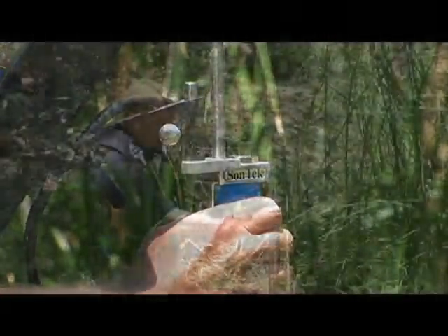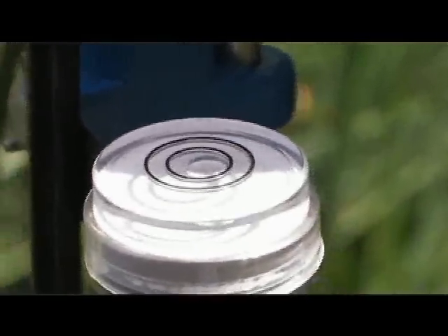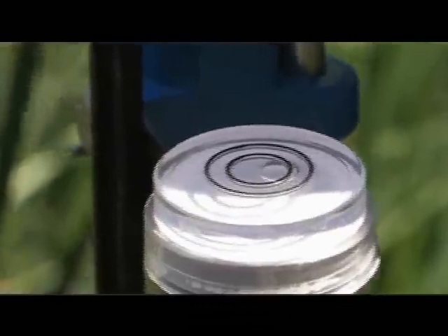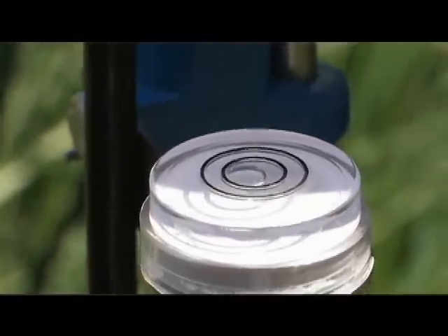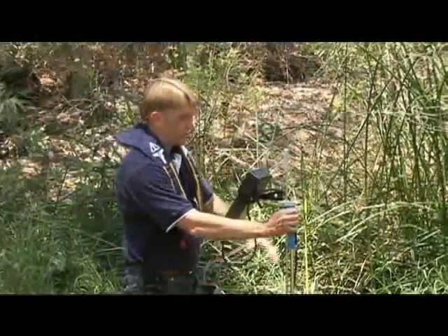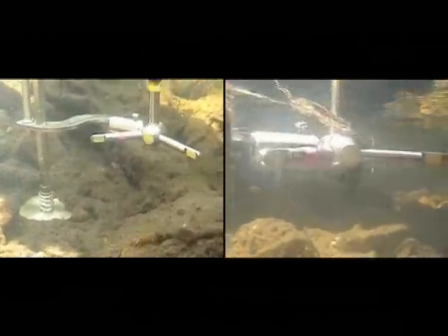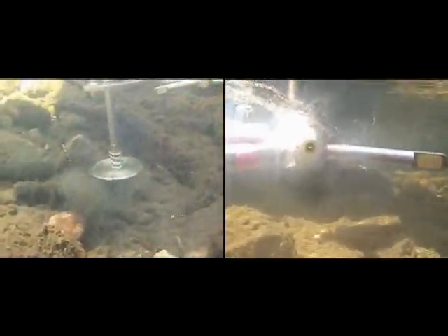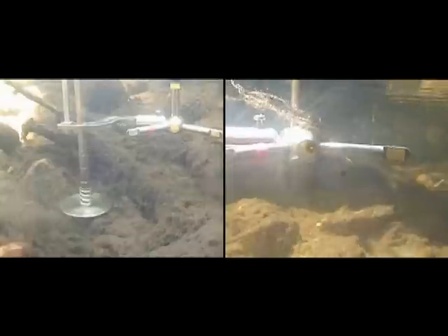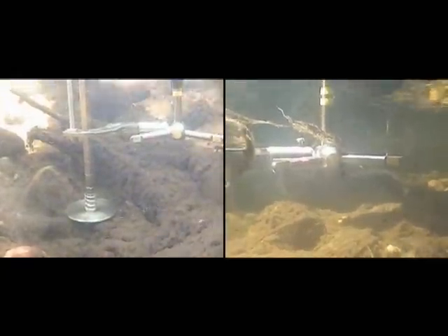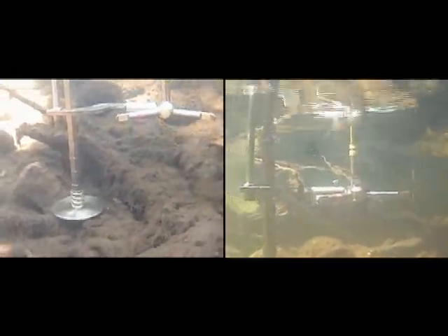While I'm making the measurement, again, because the instrument can't sense its own motion, it's very important that I keep it stable. Don't angle it during the measurement. That'll create some error. Also, if there's any debris floating down, I want to make sure that the debris stays off the probe head. Any debris that collects along the probe, number one, will disturb the velocity measurement, but also it can get in the sample volume and contaminate the signal.